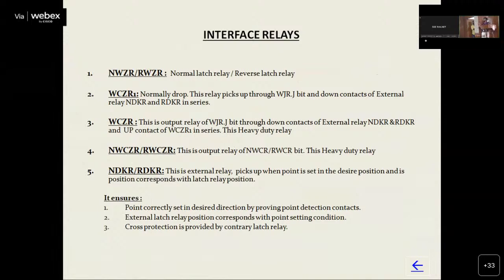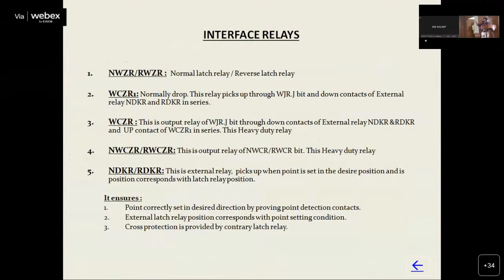Here NWZR and RWZR are latch relays, and WCZR1 is normally down, and it picks up through the WJR.J bit and the down contacts of the external relays NDKR and RDKR in series. Once both normal and reverse contacts are not available, and WJR.J, meaning that particular window of 12 seconds, is available at that time, WCZR1 is picked up. And once WCZR1 is picked up, then another relay WCZR is picked up. This is a heavy duty relay which will be utilized for extending the 110 supply.